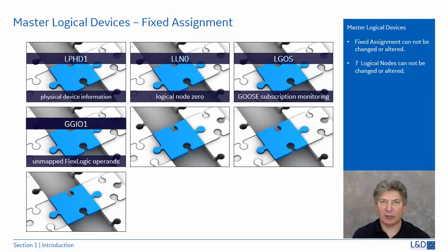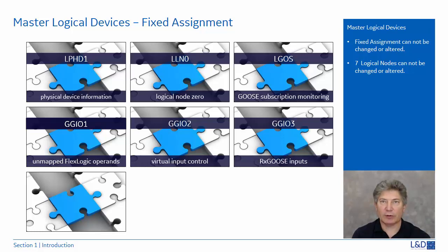GGIO1 is used for unmapped flex logic operands, such as contact I/O, brick items such as field I/O and field transducer. GGIO2 is used for virtual input control. GGIO3 is used for monitoring subscription GOOSE inputs, both analog and digital signals.